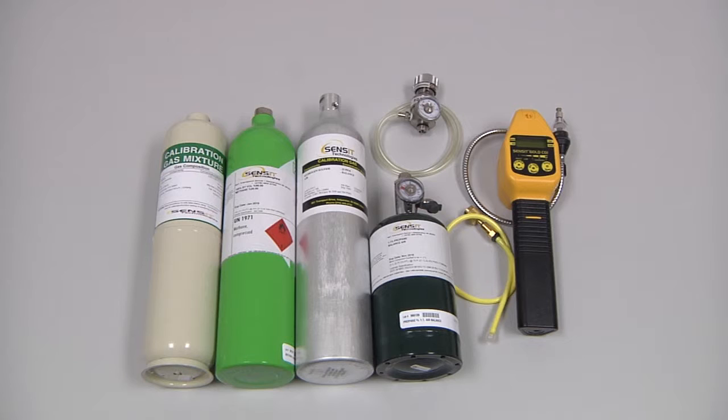This is a four gas instrument set up for natural gas, so we will need a combination bottle of 50% LEL methane and 100 parts per million carbon monoxide, a bottle of 100% by volume methane, and a bottle of 25 parts per million hydrogen sulfide. If the unit were set up for propane, we would need a bottle of 50% LEL propane, or 1.1% by volume, along with the regulator and cal adapter.